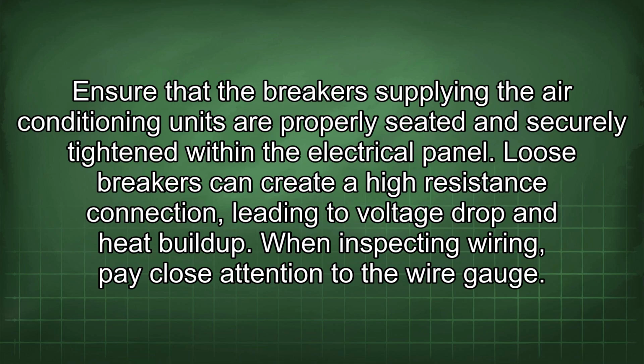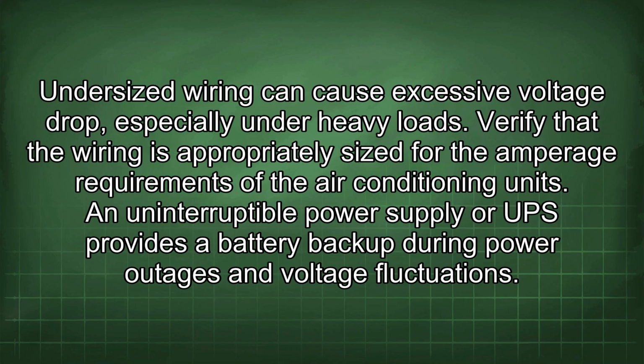Ensure that the breakers supplying the air conditioning units are properly seated and securely tightened within the electrical panel. Loose breakers can create a high resistance connection, leading to voltage drop and heat buildup. When inspecting wiring, pay close attention to the wire gauge. Undersized wiring can cause excessive voltage drop, especially under heavy loads. Verify that the wiring is appropriately sized for the amperage requirements of the air conditioning units.